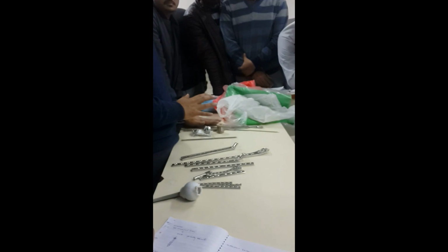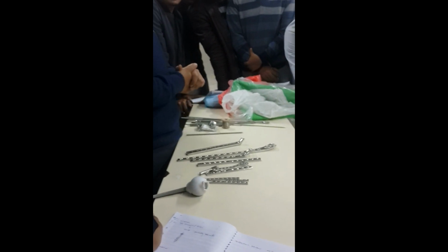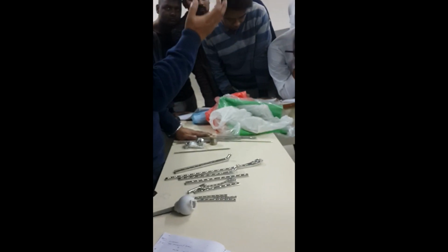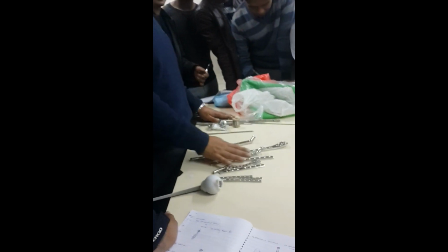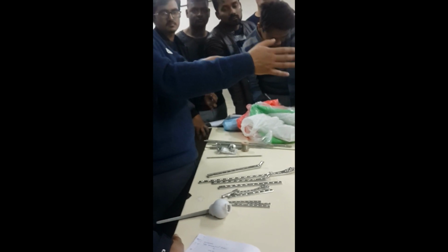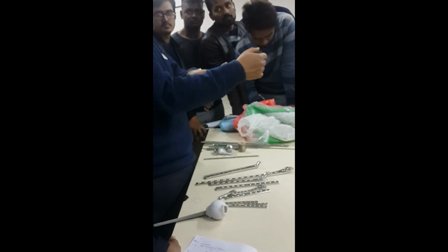So these nails are better for healing. This is based on load sharing, meaning partly taken by the bone, partly taken by the implant, and is a better healing. Absolute means like the plate, everything is taken by the plate.